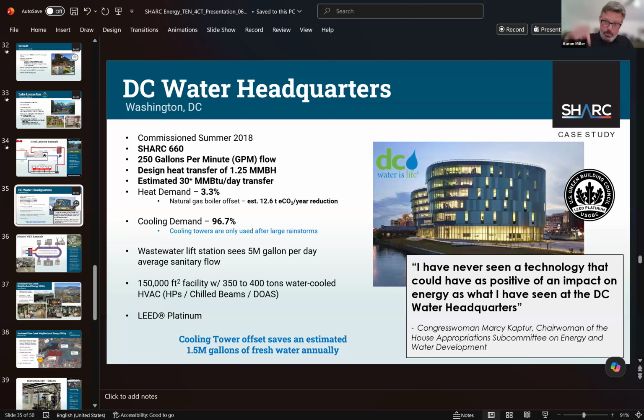The chiller plant rejects 100% of its heat into the sanitary, and then we pump it downstream to Blue Plains. What that means is that they don't ever run their cooling tower, which equates to roughly 1.5 million gallons of freshwater savings every year. Think about it, one building, over 1 million gallons of fresh water. So if you can do that at campus scale, it's pretty impressive, to the point where the military is looking at this for water scarcity and grid hardening.